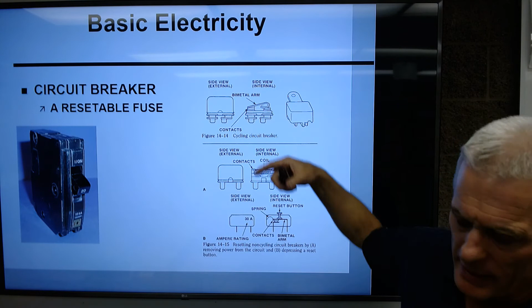What happens is, we use a bimetal arm, which is two metals with a fairly high expansion-contraction rate. As current goes across, if it flows too high and too long, it'll expand apart, breaking continuity. The load is no longer powered. This thing cools down, then contracts and goes back together, reconnects, and current starts flowing again.